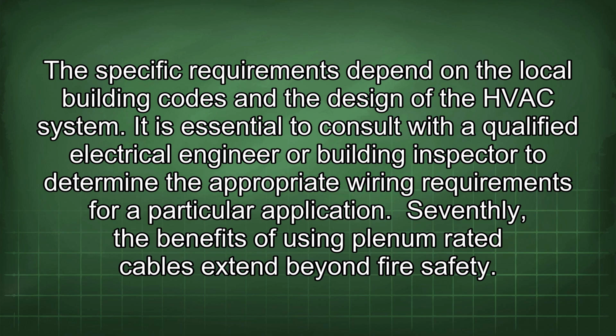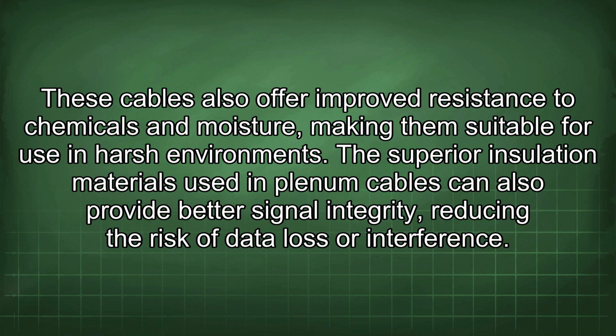Seventhly, the benefits of using plenum-rated cables extend beyond fire safety. These cables also offer improved resistance to chemicals and moisture, making them suitable for use in harsh environments. The superior insulation materials used in plenum cables can also provide better signal integrity, reducing the risk of data loss or interference.